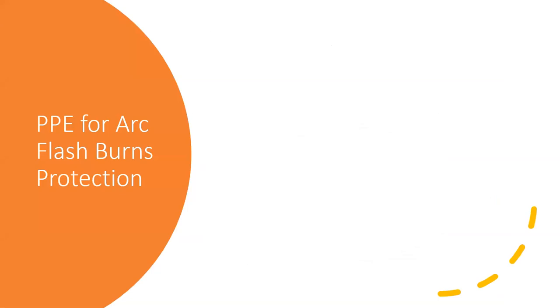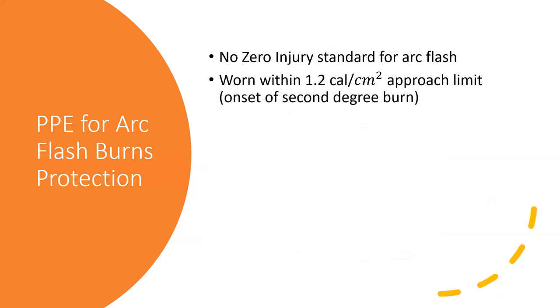So, protecting against arc flash with PPE, the first thing we must realize is that arc flash PPE is not a zero injury standard. The PPE must be worn within the 1.2 cals per square centimetre approach limit, because at 1.2 cal per square centimetre, that creates the onset of second degree burns.